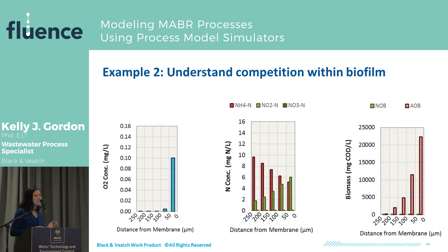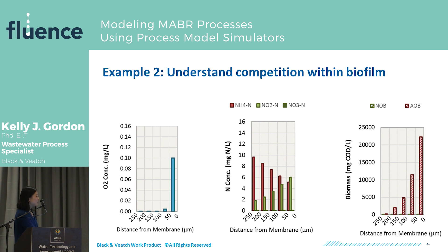This one-dimensional model could be considered almost multi-scale modeling, because not only are we able to get the gross ammonia removal rate for that module, but we're also able to understand what's going on inside the biofilm. Here I'm showing substrate profiles of oxygen, nitrogen, and biomass within the biofilm. Zero represents the biofilm layer closest to the membrane wall, and 250 microns represents the boundary between the biofilm and the bulk liquid. For the 250-micron biofilm, most of the oxygen is consumed in the inner regions closest to the membrane, and the rest of the biofilm is left anoxic. So we are both ammonia-limited and oxygen-limited in this biofilm.